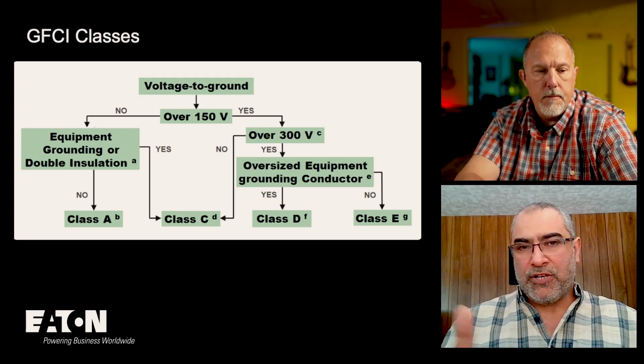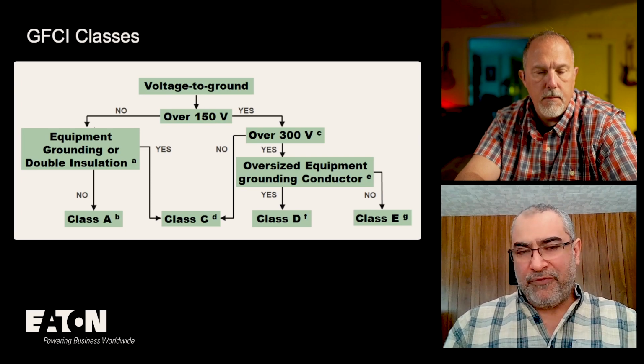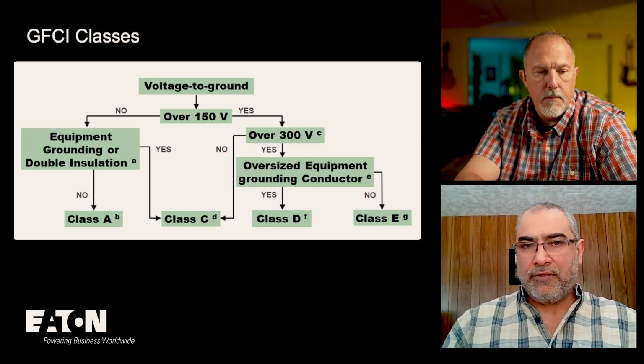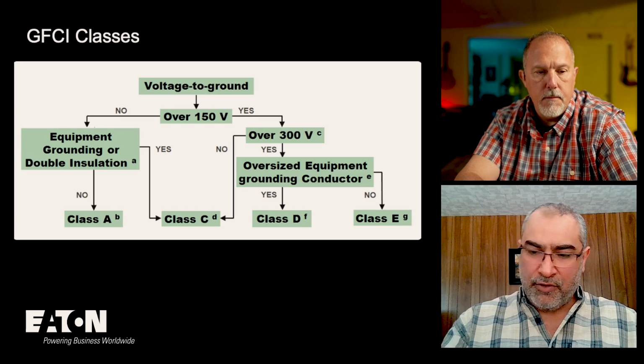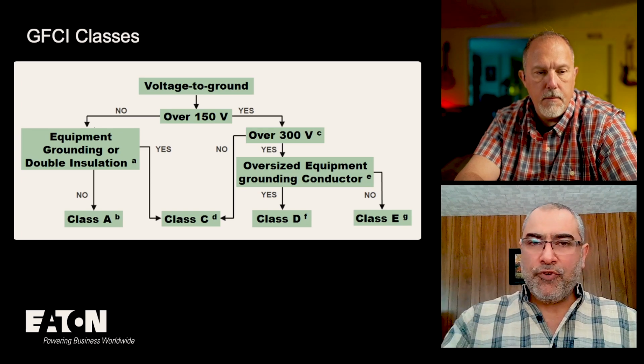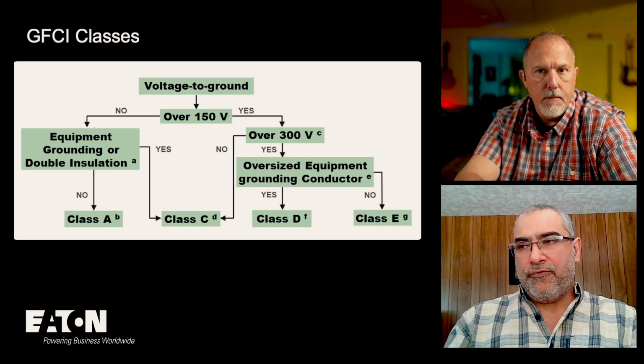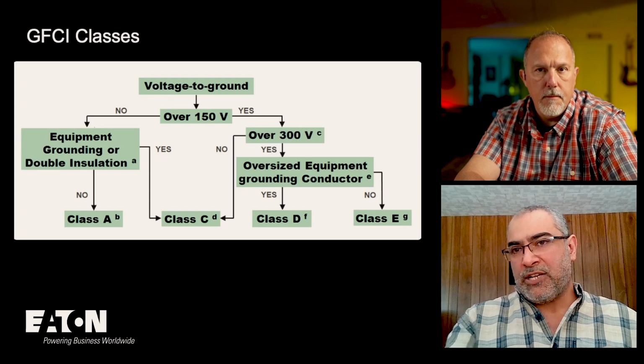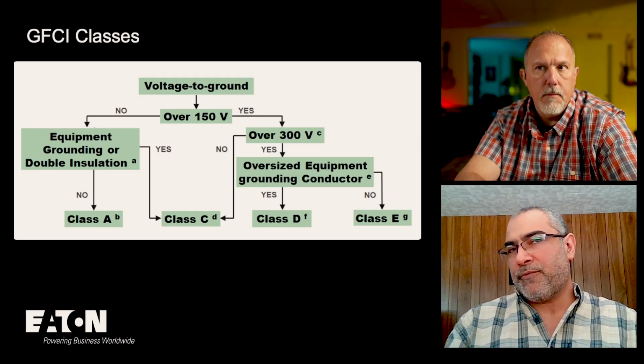But let's just focus on the higher voltage circuits. Once the voltage is more than 150 volts to ground or higher, you get to ask another question: is your voltage to ground higher than 300 volts? And this is the difference between the 480 volt systems and the 600 volt systems. 600 volt systems are more popular in Canada.